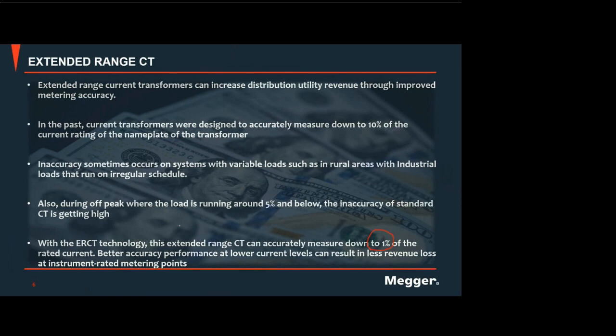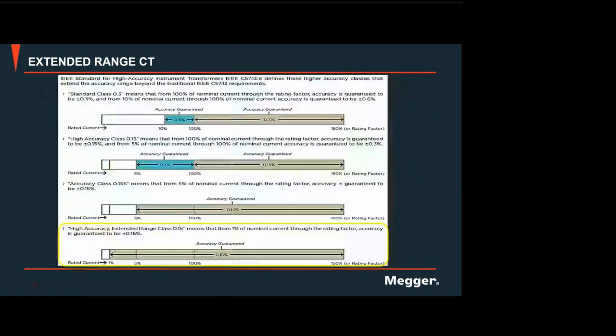So, of course, if you have this kind of accuracy, then you can perform very well at a lower current level. Looking at the standard, the C57.13.6, it discusses the different accuracy classes. So for example, here we have a class 0.3, meaning you will obtain 0.3% error from 100% of rated current up to 150%, the rating factor. Now, if you go down to 10% to 99%, then the guaranteed accuracy is only 0.6%.